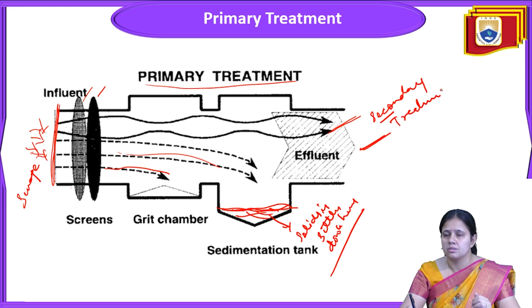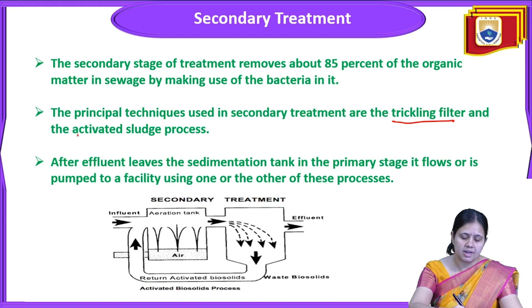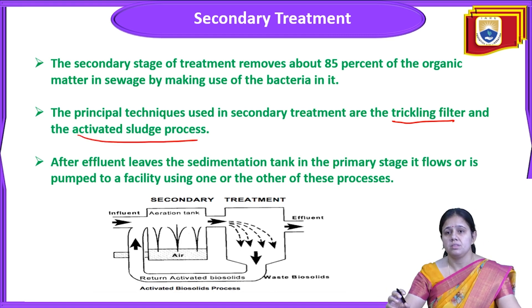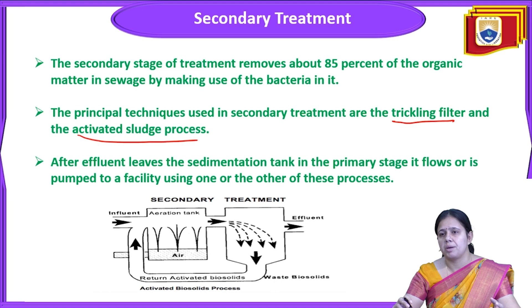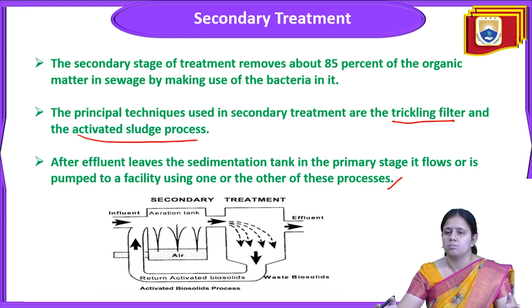Secondary treatment removes 85% of the organic matter in sewage by making use of bacteria. The principal techniques used in secondary treatment are the trickling filter and the activated sludge process. After the effluent leaves the sedimentation tank in the primary stage, it flows or is pumped to a facility using one or the other of these processes.